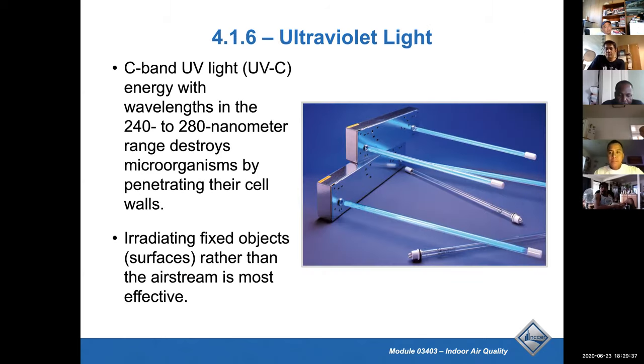If you look in a lot of homes that were built in Ewa Beach and they put in the new air conditioning, they have UV lights in them, but almost every one that's over a year old, people don't know that they need to change their light bulbs, right? Because they don't go up in the attic and they don't check on their UV lights. They'll let it go for 5 years. The light's out for 4 years. And by the time they get up there to change the light bulb, the ballast has already gone bad. So I noticed that a lot.